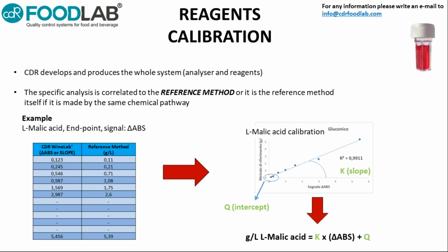Of course, we always produce the malic reagents in the same way. We have a specific internal quality control that allows us to always reproduce the very same reagents that will give us the same signal depending on the malic acid concentration. So thanks to this, we are able to put the correlation parameters, the calibration specific for this reagent, K and Q, directly into the analyzer. So we have an analyzer calibrated with a specific reagent calibrated for L-malic acid. This is the concept of the CDR calibration of the reagents.